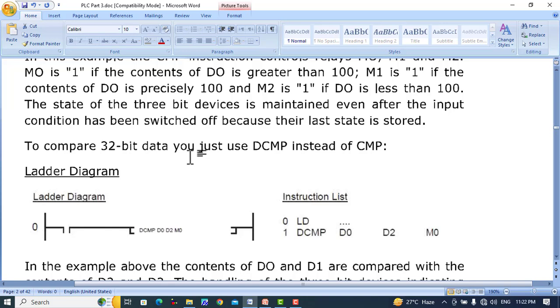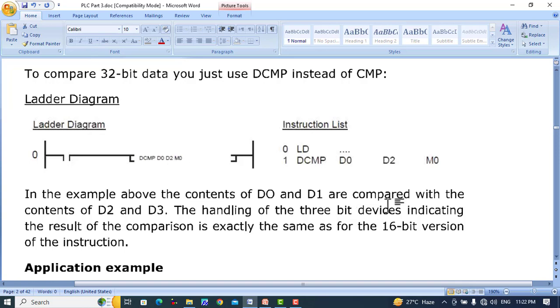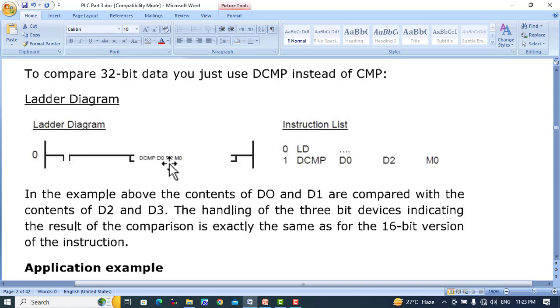In a similar way, you can also compare 32-bit data using DCMP instead of CMP. For DCMP, the command uses D0, D2, and M0. Because D0 is a 16-bit register, it will take the next consecutive register D1, so D0 and D1 are compared with D2 and D3. The handling of the three relay outputs indicating the result is exactly the same as for the 16-bit CMP instruction — M0 for greater, M1 for equal, M2 for less.